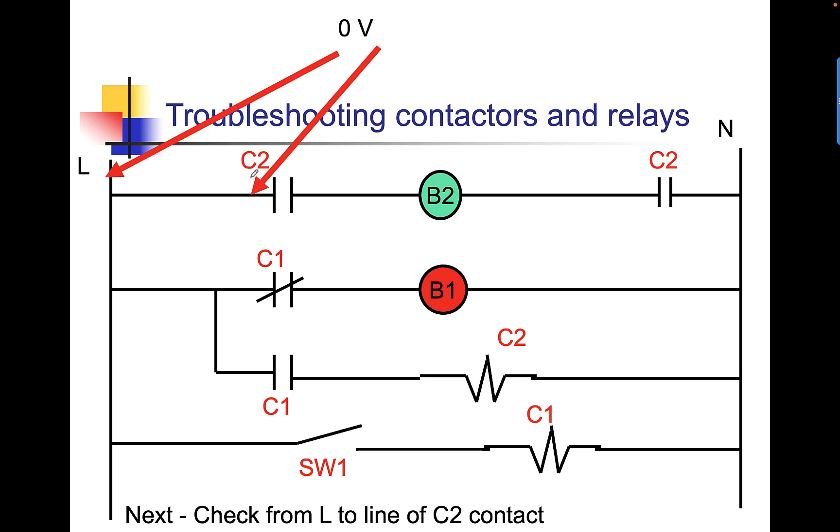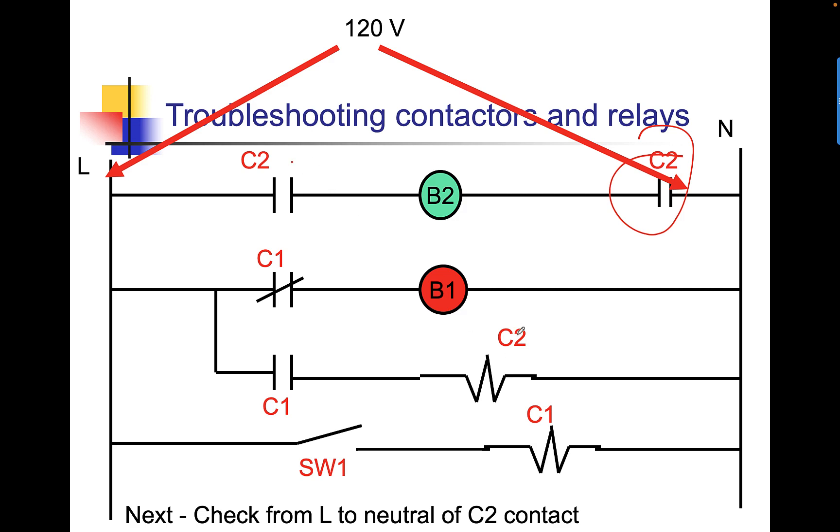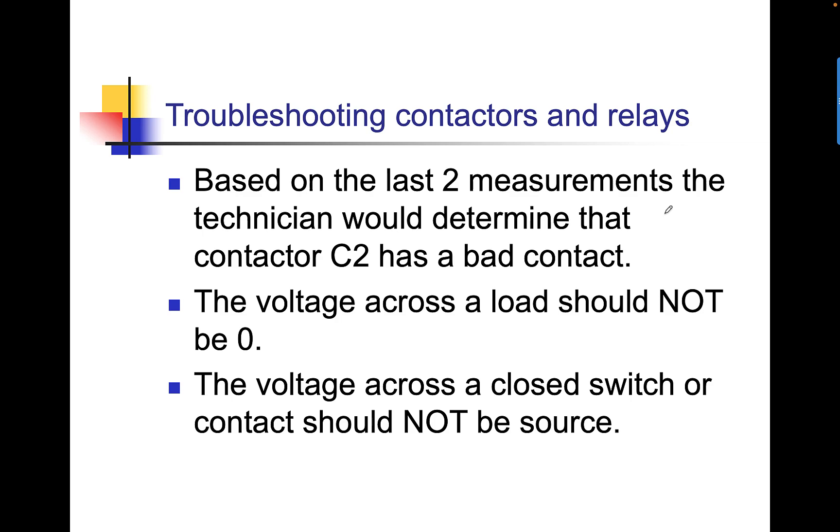Come to here. I have zero volts there. It tells me that wire is good. That tells me that the switch is closed. Zero volts across a switch tells me the switch is closed. Zero volts there. Now, wait a sec. I should have had voltage across a load. Should be what? Source, right? If we know that that's closed, I should have had source voltage in this position. But yet, I do have source here. We know what our issue is. This contact controlled by C2 is bad because the contacts are not closing. Based on the last two measurements, the technician would determine that the contactor C2 has a bad contact. The voltage across a load should not be zero. The voltage across a closed switch or contact should not be source.